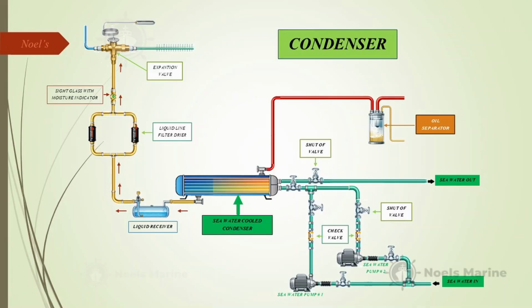Subcooled. Why is subcooling so crucial? Because it prevents the liquid from turning back into a gas too early. If it flashes back into a gas while it's still in the pipes, your efficiency drops to 0. Subcooling ensures it stays a solid column of liquid. Got it. And for reliability, the sources mentioned that there are always standby seawater pumps, right? So if one pump fails, the whole AC system doesn't just shut down. Always. Redundancy is everything at sea.